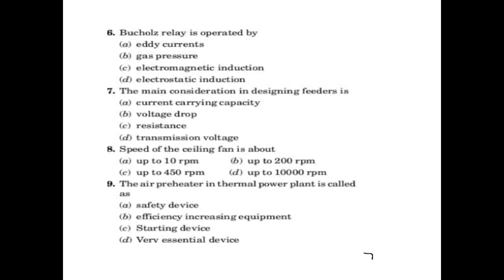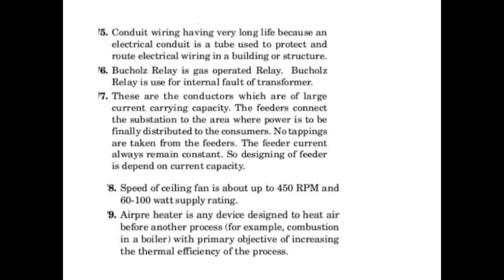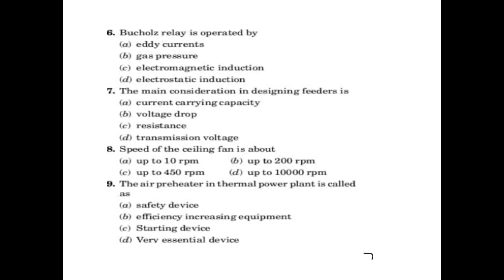The Buchholz relay is operated by gas pressure. What is the Buchholz relay in a transformer? It is a gas-actuated relay. This Buchholz relay is used for internal faults of the transformer. It detects gas pressure inside the transformer.